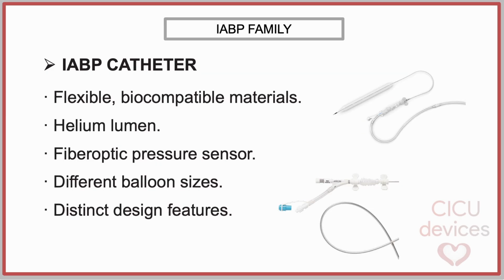The disposable IABP catheter has also evolved considerably in recent years. Modern catheters are manufactured using highly flexible, biocompatible polyurethane materials with low-profile designs that facilitate percutaneous insertion while reducing vascular complications. A major technological advancement has been the incorporation of fiber-optic pressure sensors at the catheter tip. This technology provides high-fidelity central aortic pressure monitoring without the damping and lag commonly observed with conventional fluid-filled systems. Continuous real-time pressure acquisition also improves automatic timing accuracy, particularly during arrhythmias or rapid hemodynamic changes.